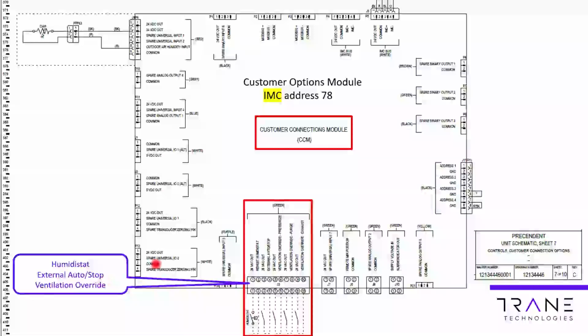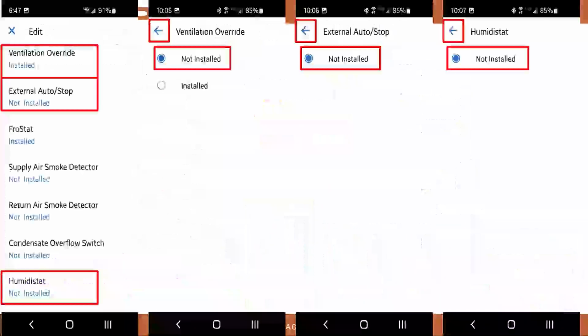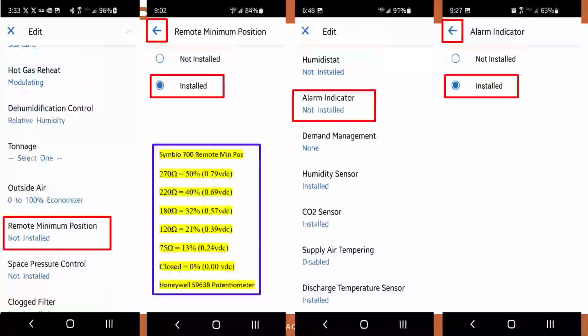Here's our external auto stop. So this comes off the customer options module. Again, I have not seen any of these unless it was ordered with the ventilation override external auto stop, and they ordered it for humidistat. So again, this is right near the Symbio 700 control board. A remote minimum position also comes off of that board.